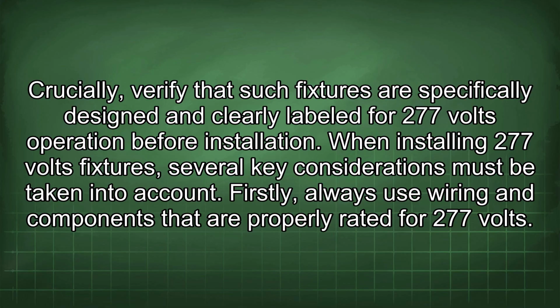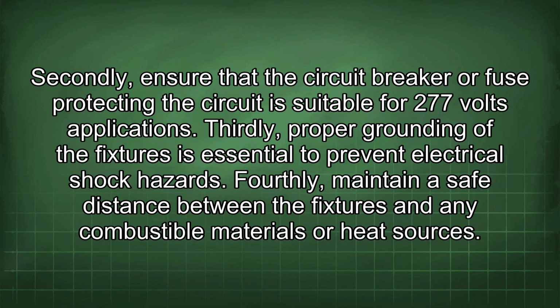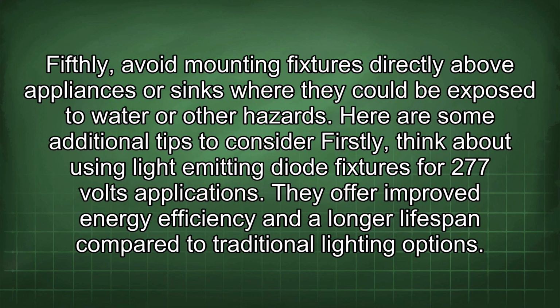When installing 277 volts fixtures, several key considerations must be taken into account. Firstly, always use wiring and components that are properly rated for 277 volts. Secondly, ensure that the circuit breaker or fuse protecting the circuit is suitable for 277 volts applications. Thirdly, proper grounding of the fixtures is essential to prevent electrical shock hazards. Fourthly, maintain a safe distance between the fixtures and any combustible materials or heat sources. Fifthly, avoid mounting fixtures directly above appliances or sinks where they could be exposed to water or other hazards.